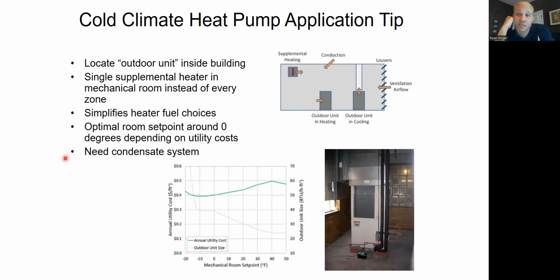One, if it's an existing building with an existing heating system and they got like hot water baseboard going around, just keep the hot water baseboard. Use that as your supplemental heat. Run the heat pump on all the normal hours, and when it gets really cold outside, the boiler will kick on and feed hot water to the baseboard heaters, right? Or radiators or whatever you happen to have already there, right? On your other heating sources. Or if you have electric baseboard, same idea. You run that when the heat pump can't keep up.